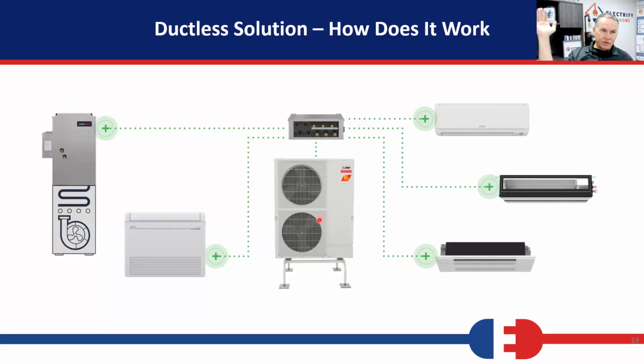So these things can only slow down so far because they need to have oil returned back to the system. So if I've got a system here that'll only slow down to 20,000 BTUs, and I've told that customer, oh, this is a great idea because you've got room-by-room temperature control, and that customer is thinking in his head, great, I can just run the master bedroom and I don't have to heat and cool the rest of my house. They get an idea that this is going to be a super efficient way of doing it.